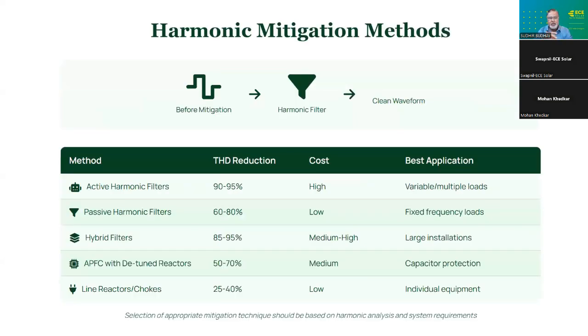To mitigate harmonics, the first solution, definitely, if you want to reduce by 95%, is an active harmonic filter. Cost is very high, but it can handle multiple loads and variable loads. The second option, relatively low cost, is passive harmonic filters, which will block up to 60 to 80%. We can go in for a hybrid combination also. Or, as I said, we can go in for APFC with detuned reactors, which will solve up to 50 to 70% of the harmonic problem. So this is how we have to address the problems of the future as regards LT consumers, and that too with solar integration in the coming future.